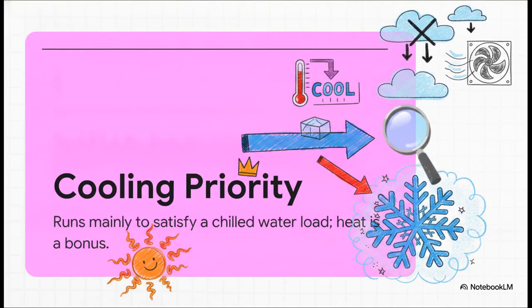To answer that question effectively, you need a brain. Depending on the design, these systems can be set up in a couple of different ways. First up is cooling priority. In this operational mode, the chiller runs primarily to satisfy a chilled water load. Basically, cooling is the boss here. It recovers heat only if a useful heating load happens to be available. If there's no heating load right then, the system just rejects the excess heat like a normal chiller would. Heating is just treated as this highly efficient, happy bonus.